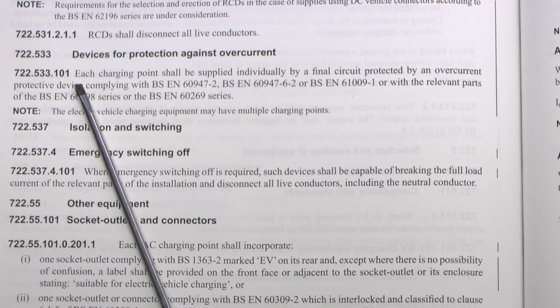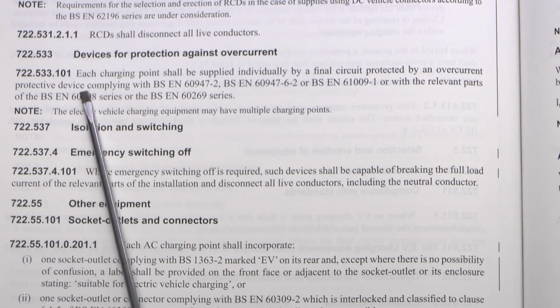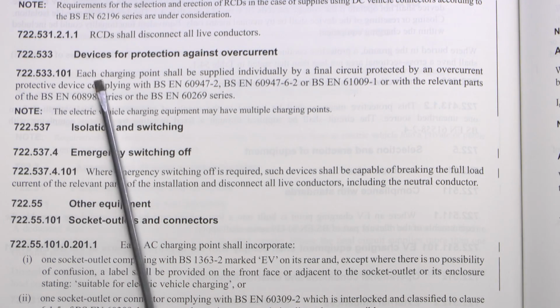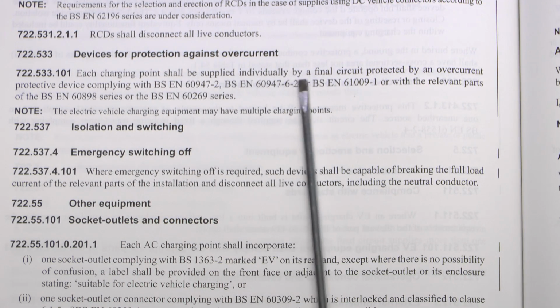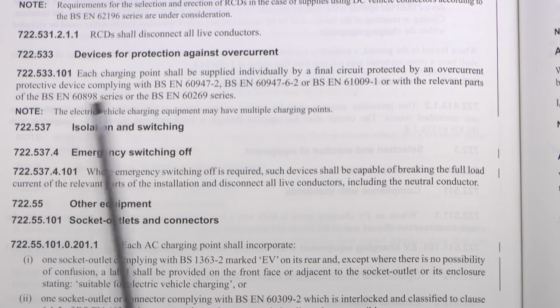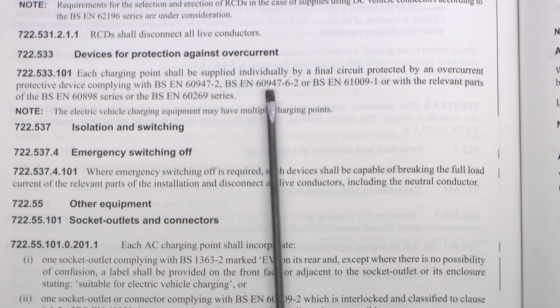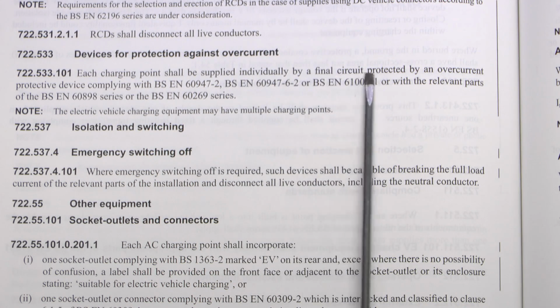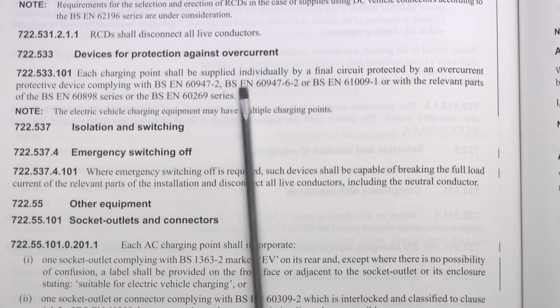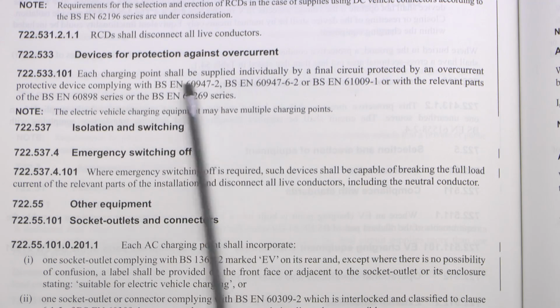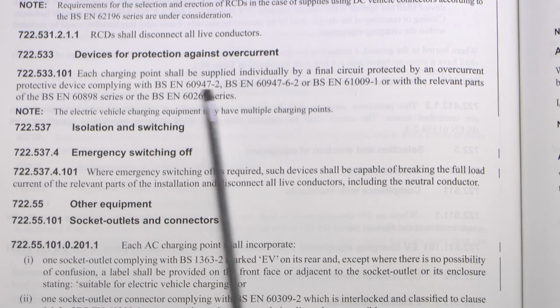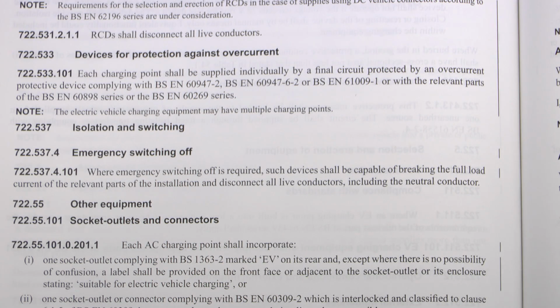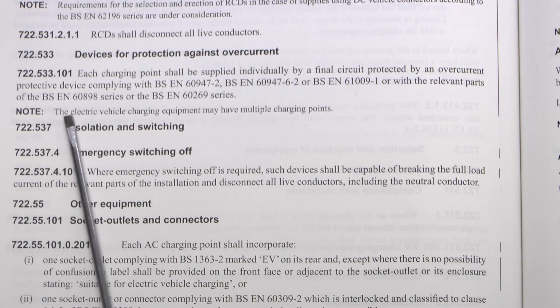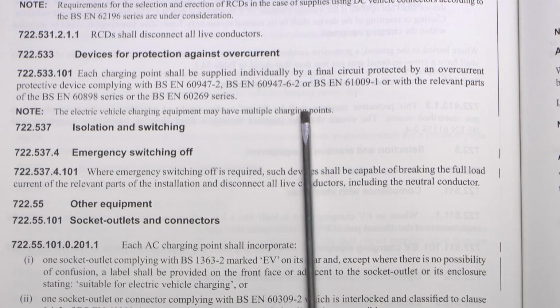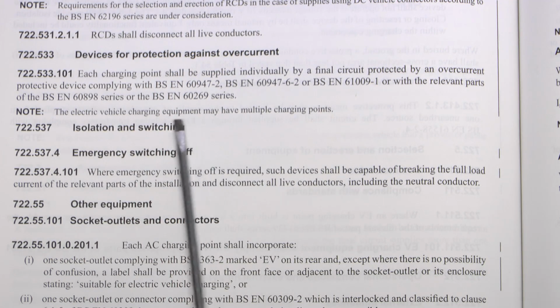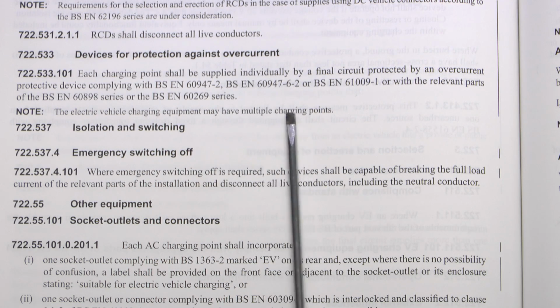And another item here, which is a new one, 722.533.101. Each charging point shall be supplied individually by a final circuit protected by an overcurrent protective device, complying with one of the various standards here. So no just tapping it onto some of the existing circuit, an individual circuit for each one. And if you have multiple charging points, then they all need their own individual circuit supplied by their own individual protective device. Although, as we've got a note here, the electric vehicle charging equipment may have multiple charging points, so it's not necessarily incorrect to have several of them within the same piece of equipment.